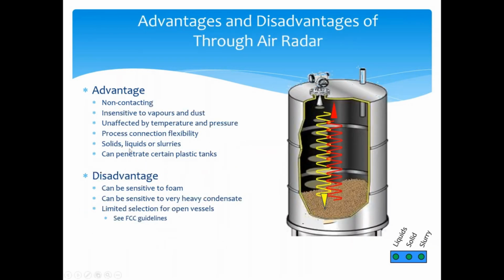Radar, you're going to see a lot of the same advantages. Non-contacting, the big differences are we don't care if there's vapor or dust in there, unaffected by changes in temperature or pressure, and we can do all three of the solids, liquids, or slurries with no issues. And we'll talk about this a little bit later when we look at individual applications, but we can penetrate through plastic tanks. Disadvantage, can still be sensitive to foam, really heavy condensate, and the FCC guidelines that somebody asked about earlier.